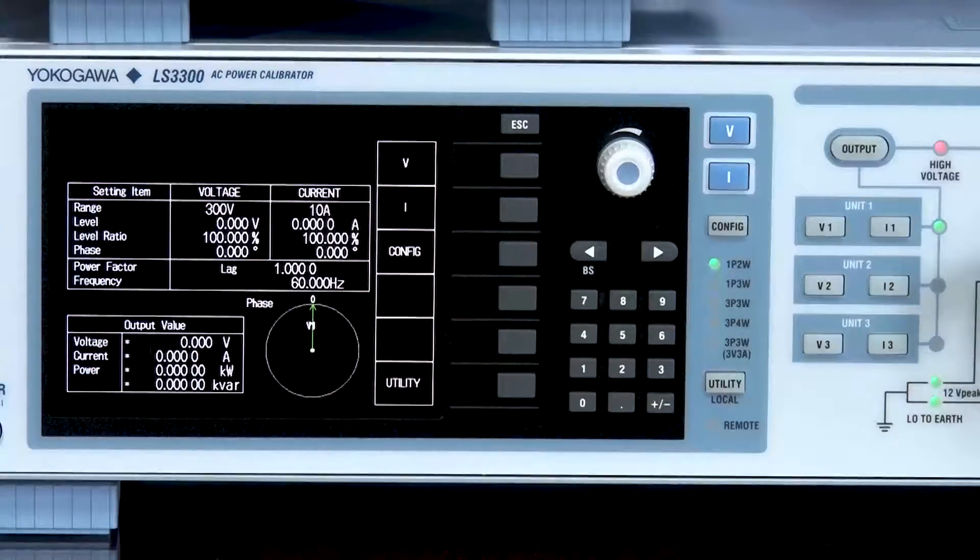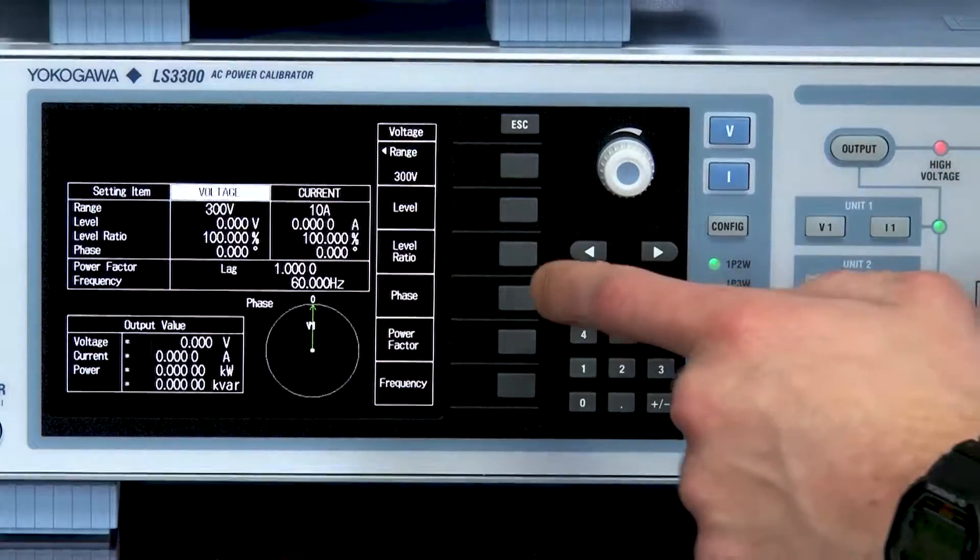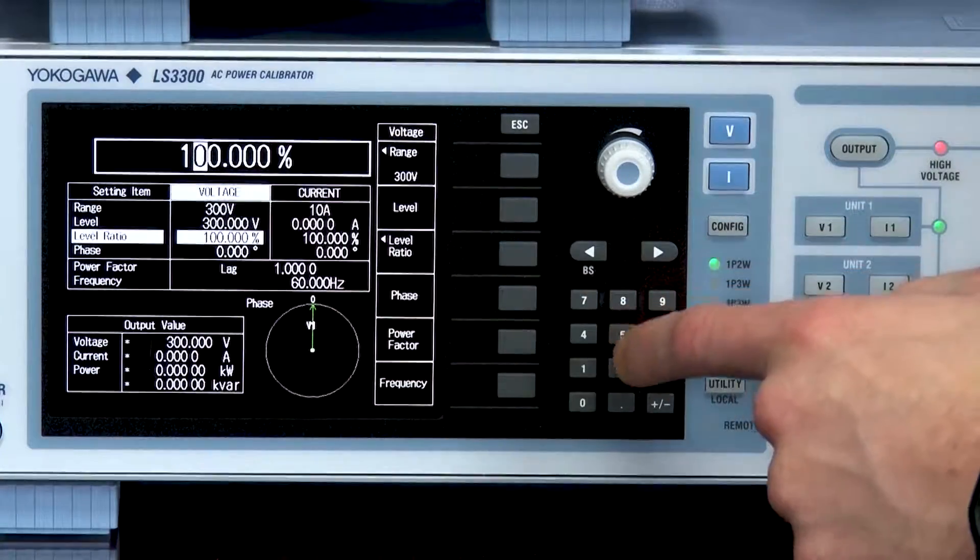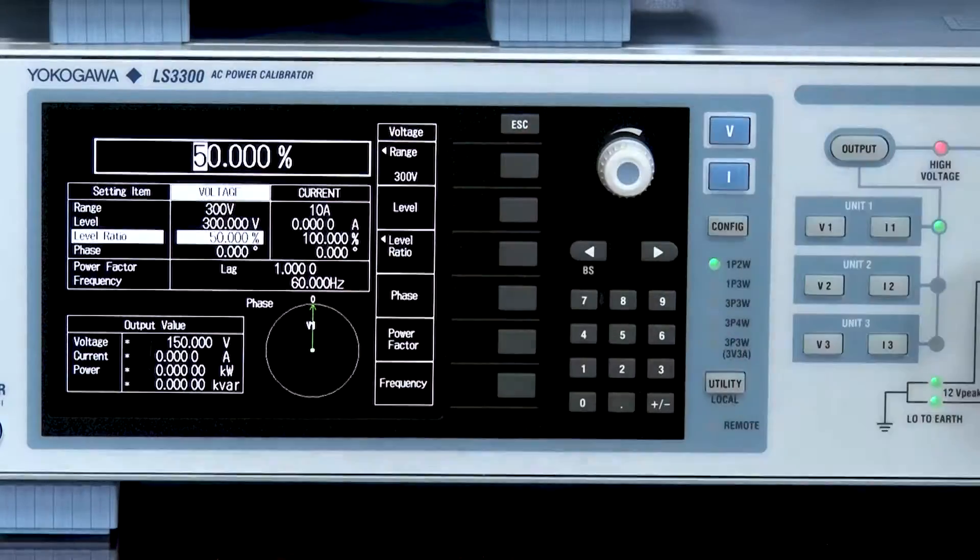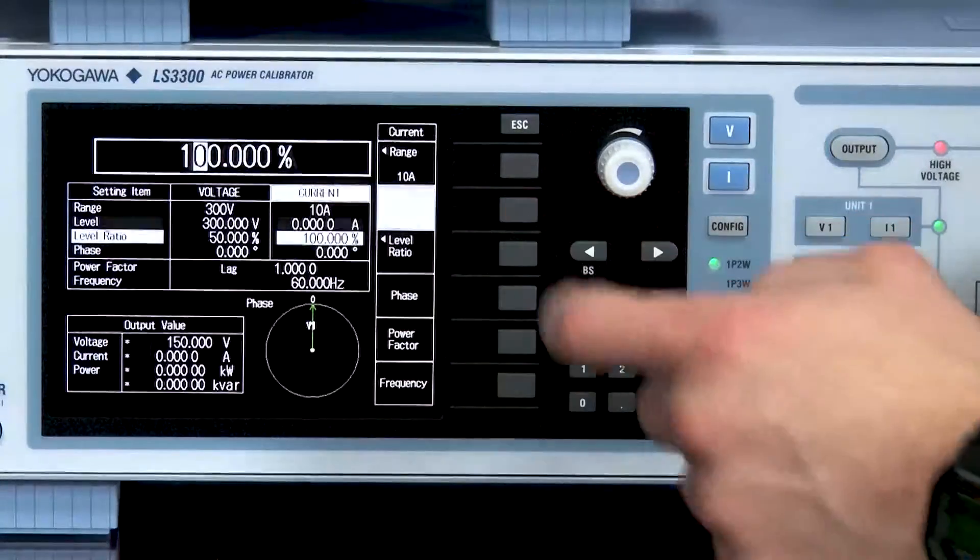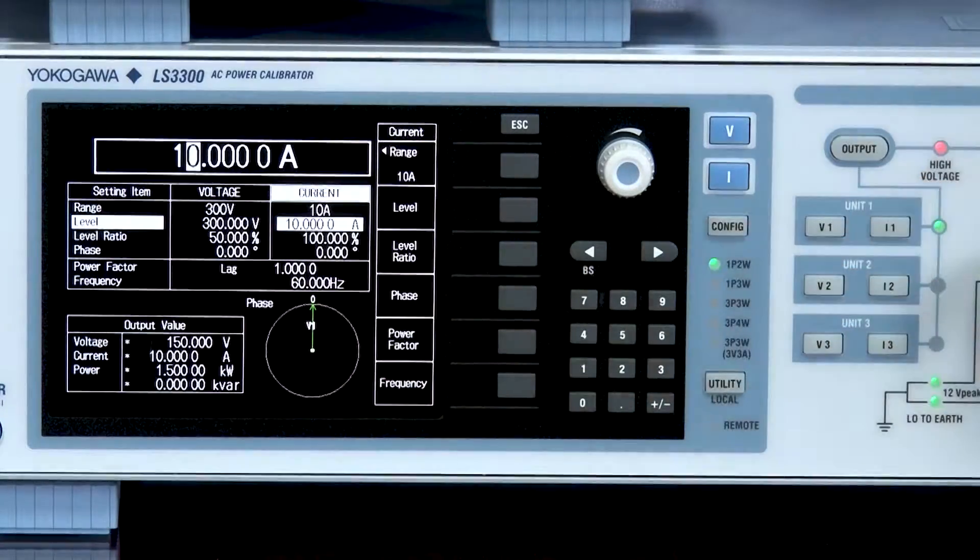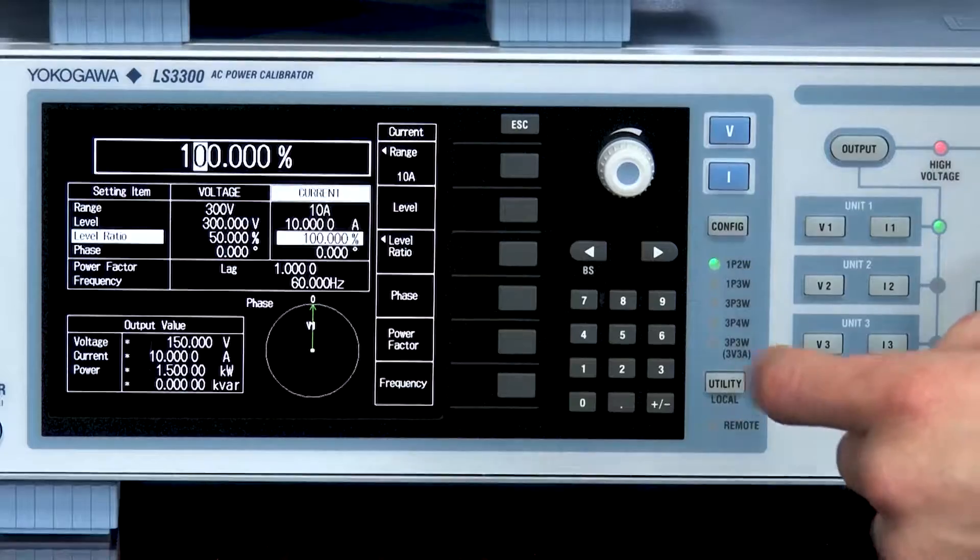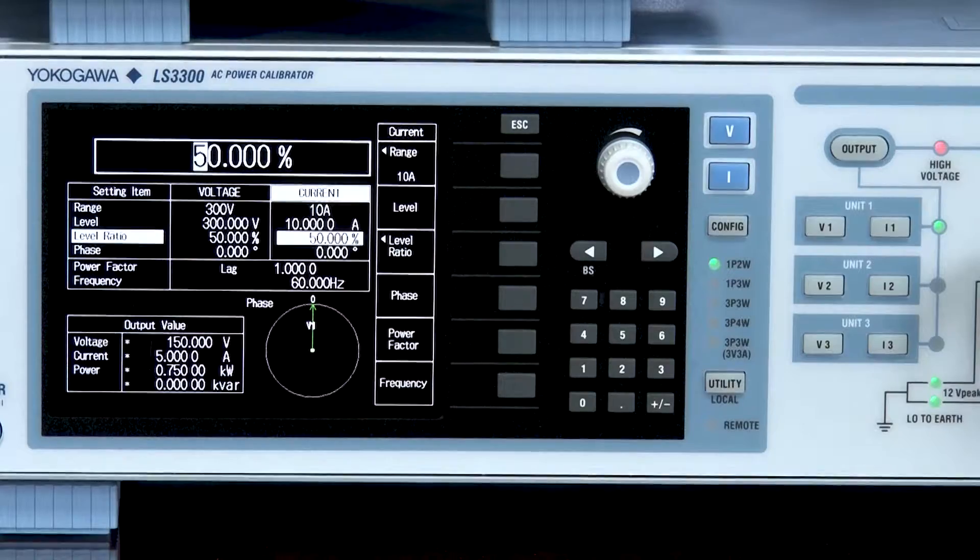To begin the test I will set the output level of voltage to 300 volts by selecting the voltage key and entering in 300 volts under the level option. Next I will select the level ratio, enter in 50%, and click enter. This will provide me with an output of 150 volts. Next I will go into the current menu. I will set the level to 10 amps by going to level and entering in 10 amps. Next I will set the level ratio to 50% and enter, which will provide me an output of 5 amps.